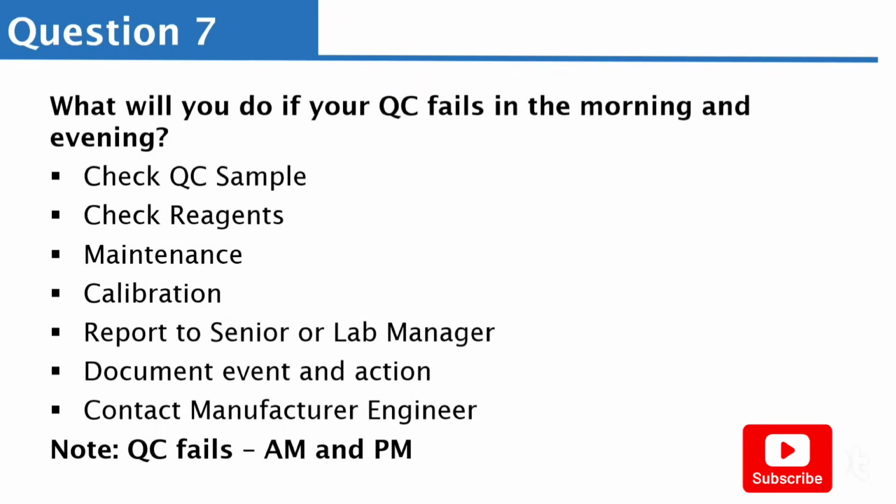So there may be something happening in the analyzer, like the channels, as the case may be, and that should be taken care of. Or maybe the reagent can be sensitive to light or sensitive to time, as the case may be, and that can explain why the QC should fail 2 times a day.